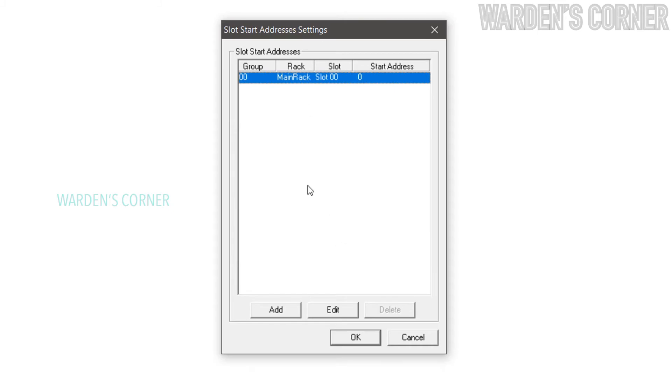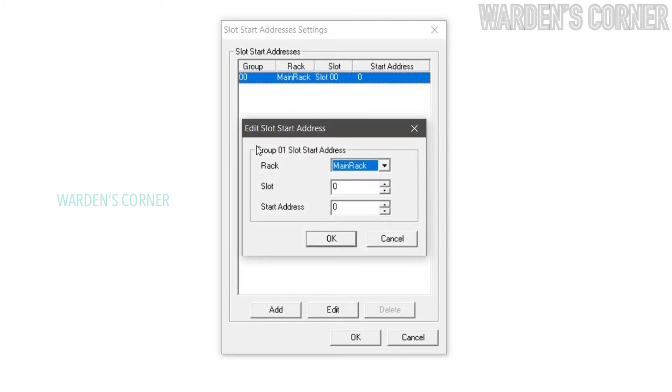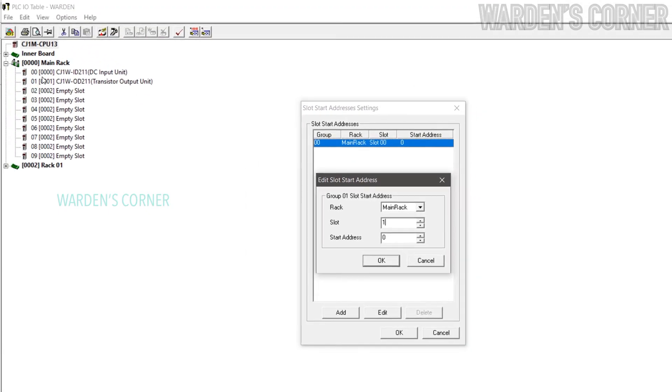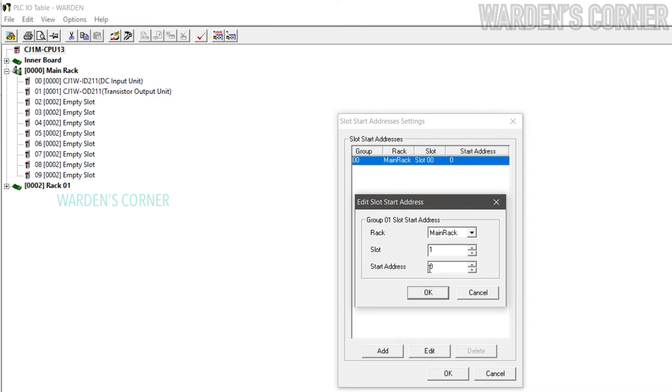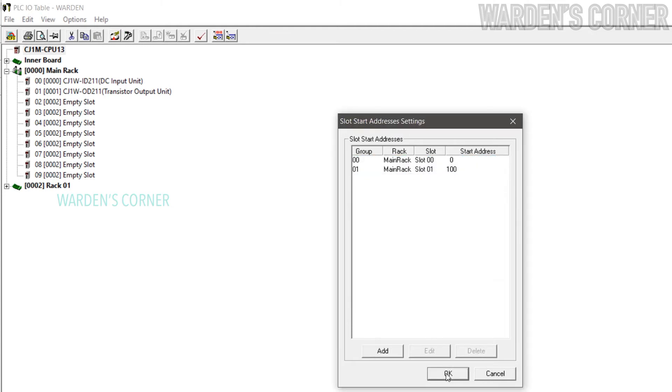And click Add icon to set the output card. Change Slot 0 to 1, because that is the output card location or designation. Some PLCs use 10CH or 11CH like CPM1A PLC model, and CP1A series uses 100CH or 101CH. So let's start with a 100 channel address for the output card. Click OK, OK.